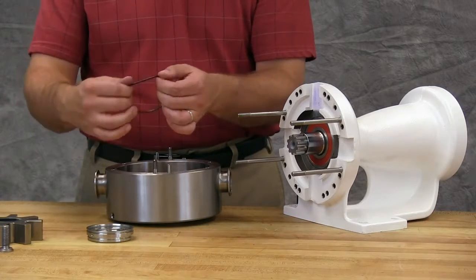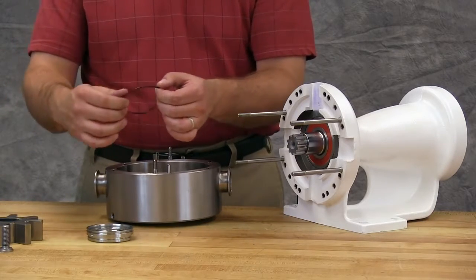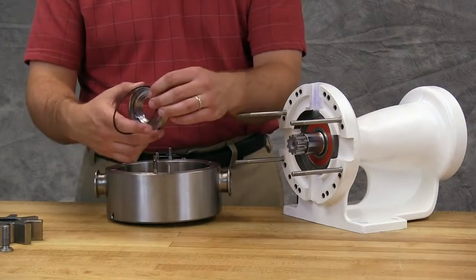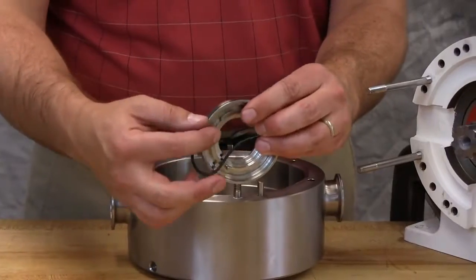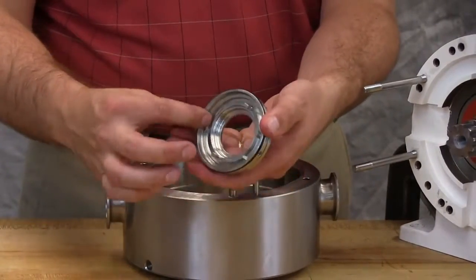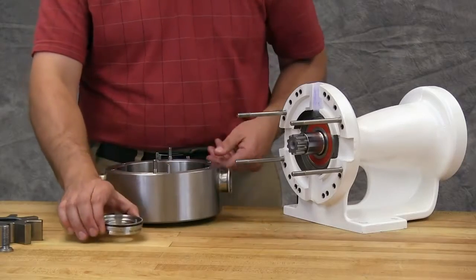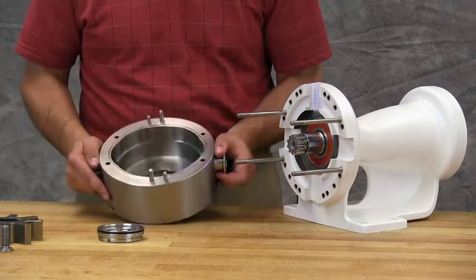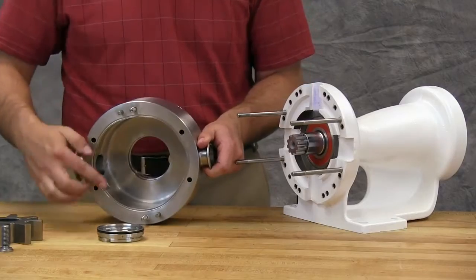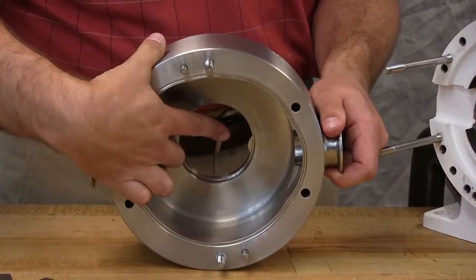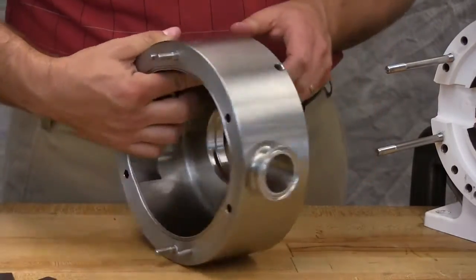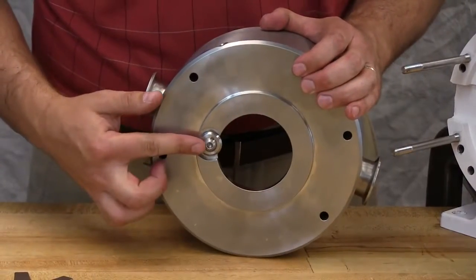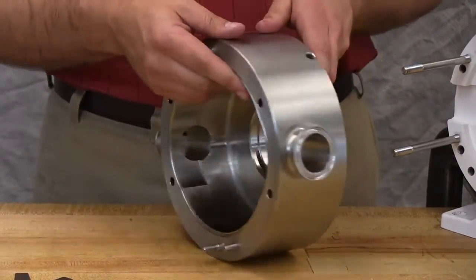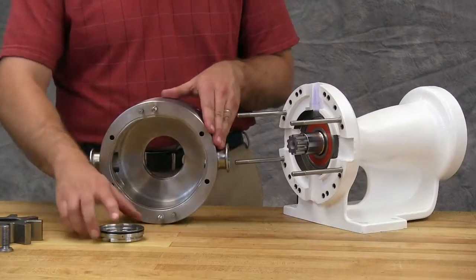All O-rings should be lightly lubricated with a food-grade lubricant that is suitable for the application before installing. If the seal housing was removed from the casing, install the seal housing O-ring onto the seal housing. When installing the seal housing into the casing, the anti-rotation cutout of the seal housing must line up with the anti-rotation washer on the backside of the casing.